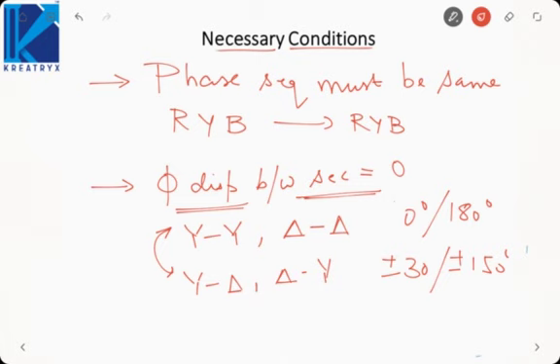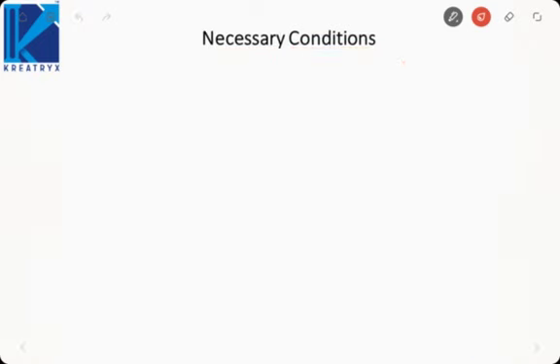These are the four necessary conditions that must be satisfied before connecting the two transformers in parallel. If you do not satisfy these conditions, then parallel operation will not be possible, or it will not work under desirable condition, or it will not work as required. Okay, requirements will not be met. Now these are necessary conditions. Okay, let us summarize those. First one was same voltage rating.